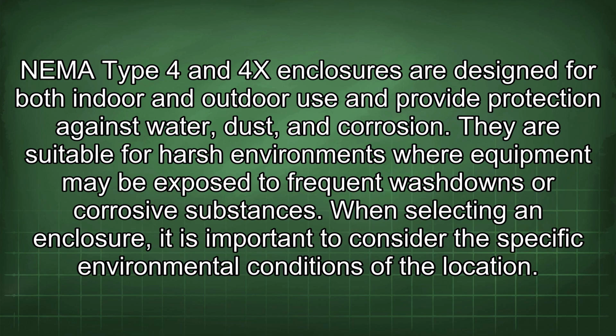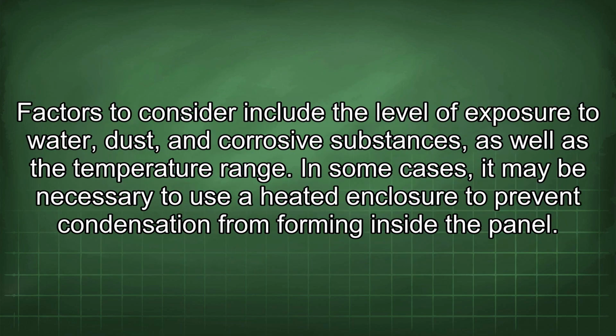NEMA Type 4 and 4X enclosures are designed for both indoor and outdoor use and provide protection against water, dust, and corrosion. They are suitable for harsh environments where equipment may be exposed to frequent washdowns or corrosive substances. When selecting an enclosure, it is important to consider the specific environmental conditions of the location. Factors to consider include the level of exposure to water, dust, and corrosive substances, as well as the temperature range. In some cases, it may be necessary to use a heated enclosure to prevent condensation from forming inside the panel.